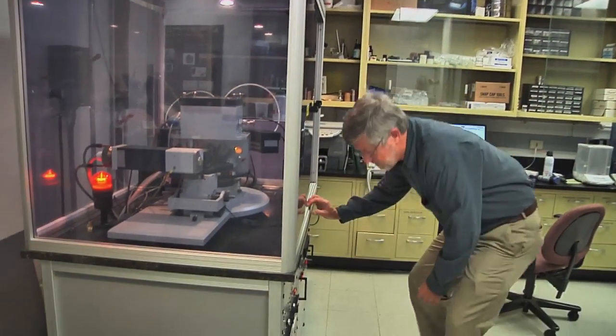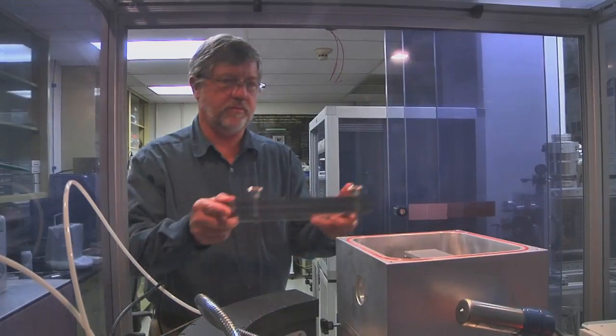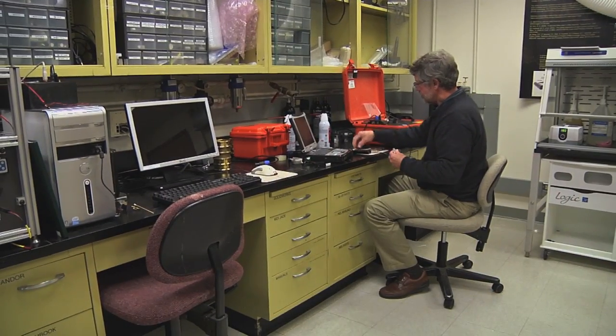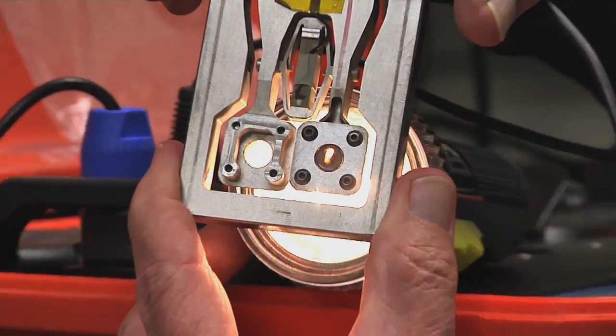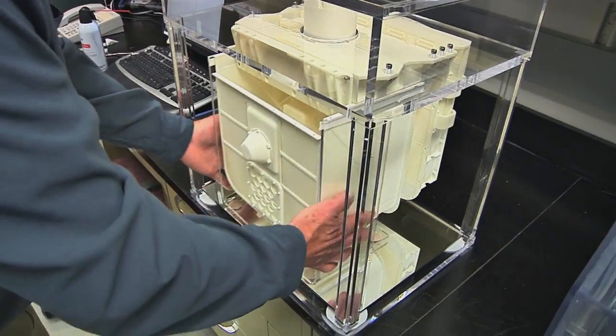How do you get a laboratory to fit on a rover going to another planet? You have to make it small, with a lot less mass. A regular diffractometer lab is about double-wide refrigerator-sized with lots of complicated motions of the detector, sample, and source. We had a new idea where we actually vibrate the sample with a tuning fork, so the sample does all the motions and the machine doesn't have to. We essentially went from a complicated, big machine with many moving parts to a small, simple machine with no moving parts.